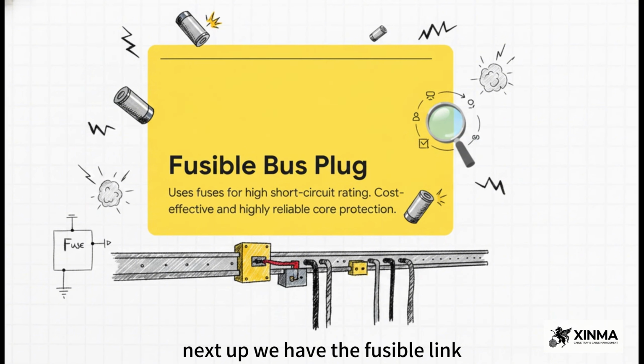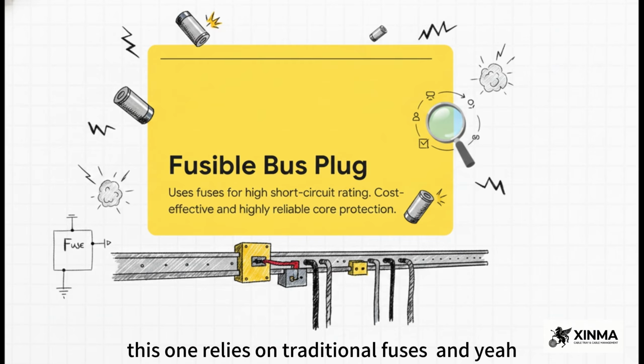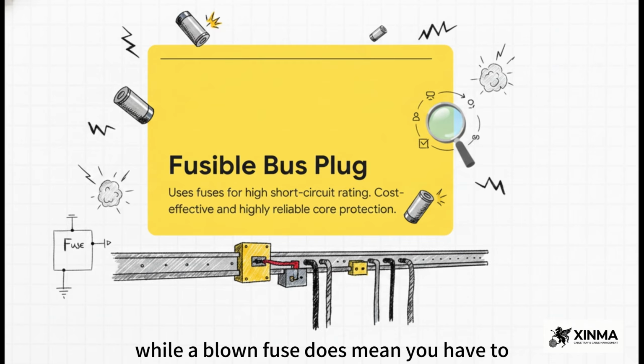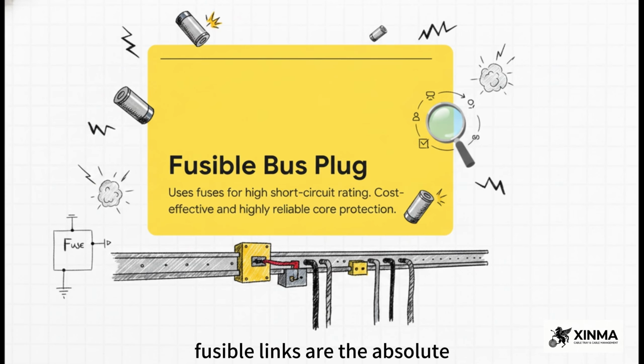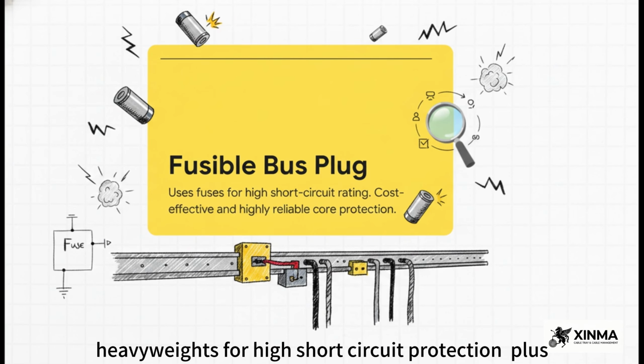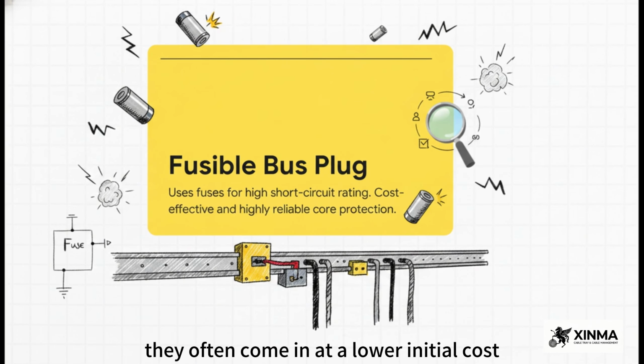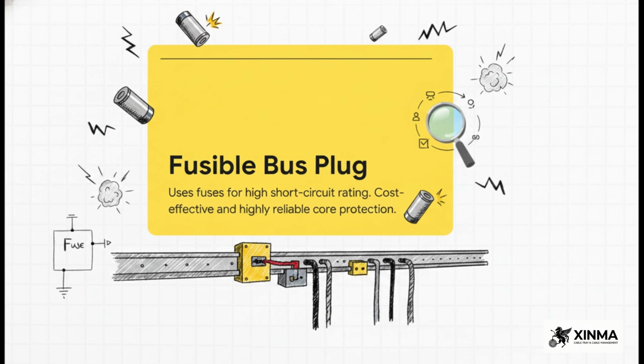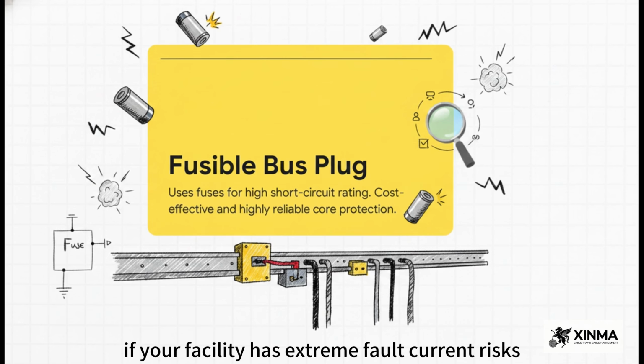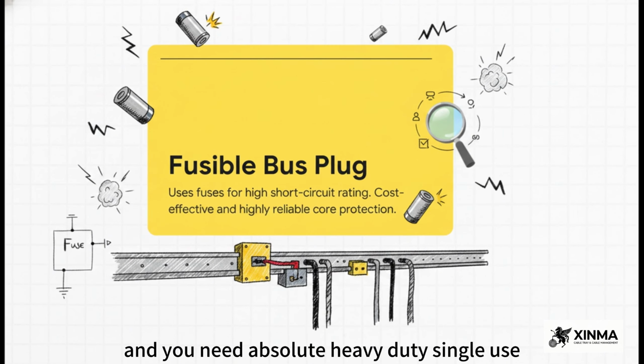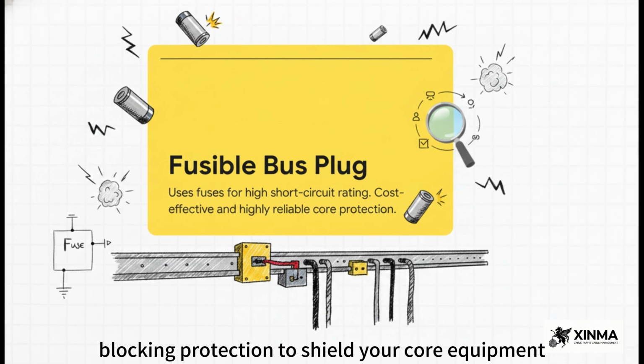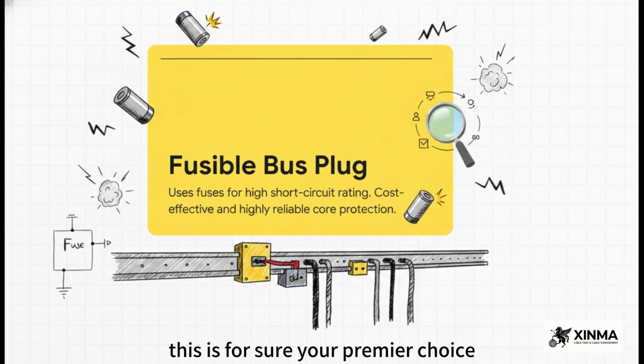Next up, we have the fusible bus plug. Now, unlike the breaker type, this one relies on traditional fuses. And yeah, while a blown fuse does mean you have to physically get in there and replace it, fusible plugs are the absolute heavyweights for high short-circuit protection. Plus, they often come in at a lower initial cost. If your facility has extreme fault current risks and you need absolute, heavy-duty, single-use blocking protection to shield your core equipment, this is for sure your premier choice.